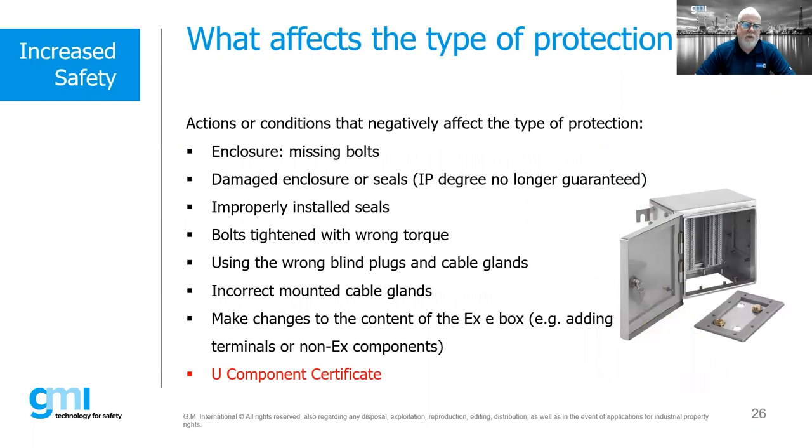Some downsides of increased safety: missing bolts, damaged seals, improperly installed seals — replacing seals with sealant is not acceptable. Bolts tightened with the wrong torque. Using the wrong plugs and cable glands — though almost every cable gland available will be Ex e. Not mounting cable glands correctly or using wrong accessories. Making changes to the box contents — adding terminals or non-EX components. Again, using a U component certificate on a non-assembly-certified box populated with EX terminals is not compliant — it must be certified as a complete assembly.